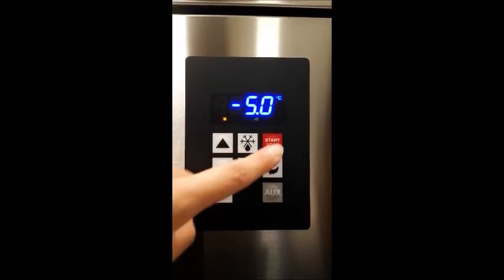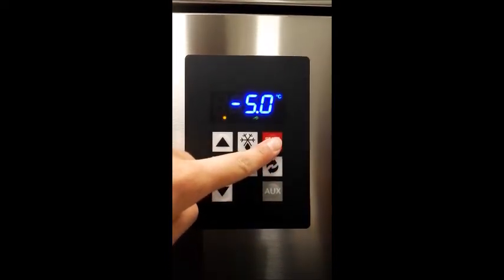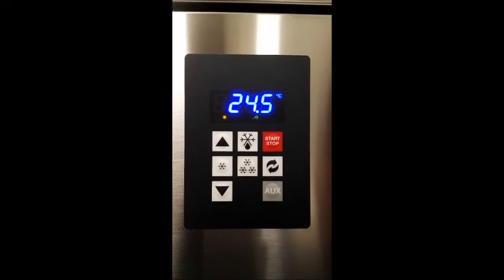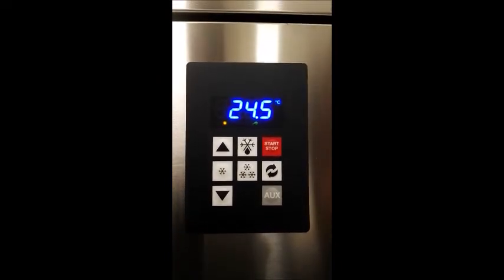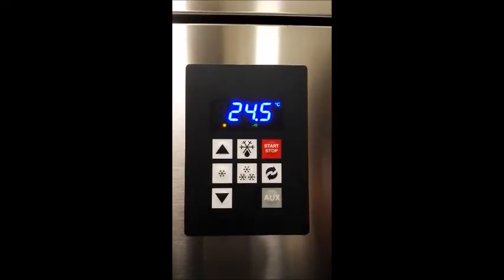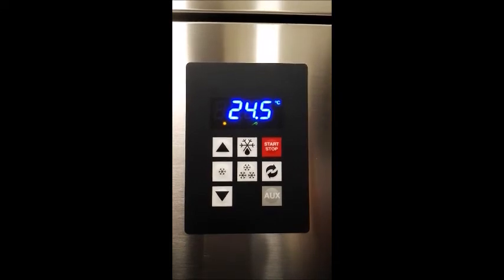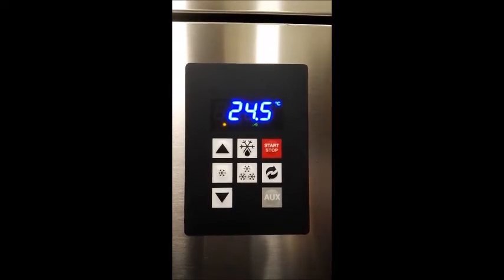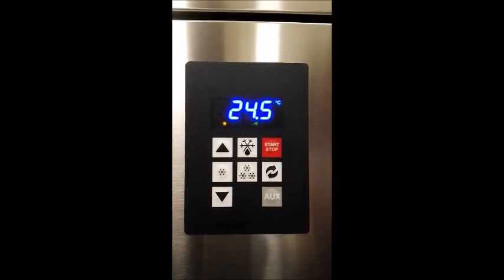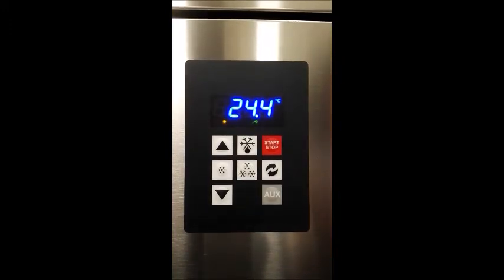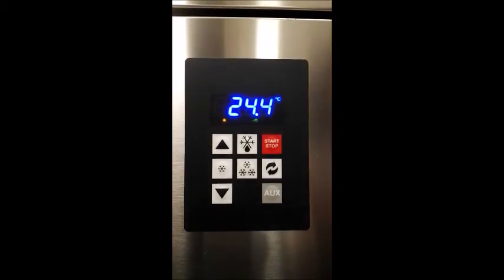Now, pressing the start button, we are going to start the selected cycle. Once the cycle is confirmed, the device does an automatic identification of the probe's insertion, around 2 minutes, at the end of which, if the device doesn't recognize the core probe, it switches to a time cycle automatically.